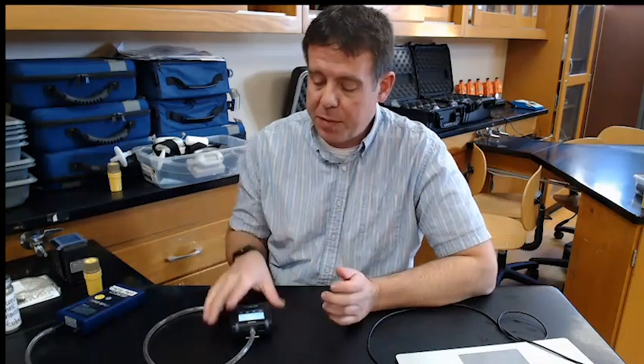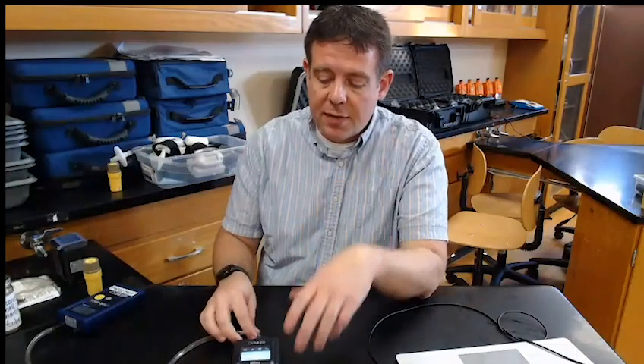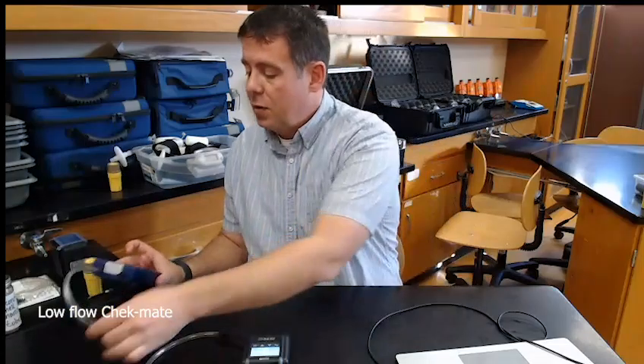Today we are going to use a pocket air pump from SKC. So this is going to be a low flow. Think of low flow with gases and vapors, so about 0.2 liters per minute for a lot of VOCs, which equates to about 200 milliliters per minute. And so we are going to use chek-mate on this.